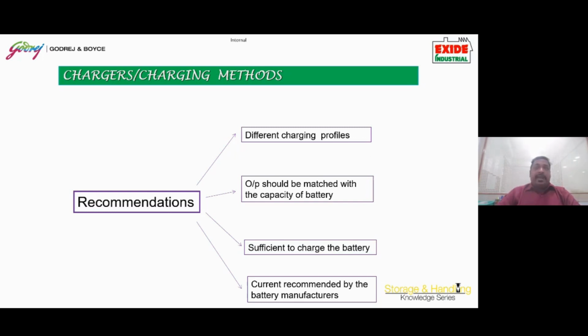So which means that if I am charging a 600 Ah battery, the charger should be able to deliver at least 20% of 600, that is at least 120 amperes. It should be able to deliver. If it is not able to deliver anything less, up to even 10%, then the charger will not be able to charge the battery in the next 12 hours or 10 hours, whatever is the recharging time.